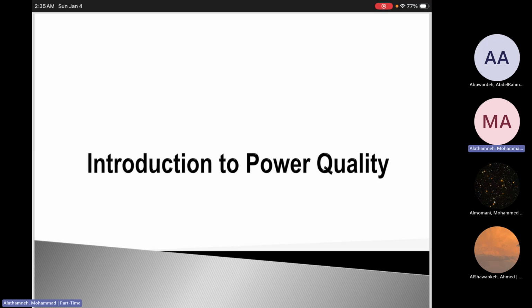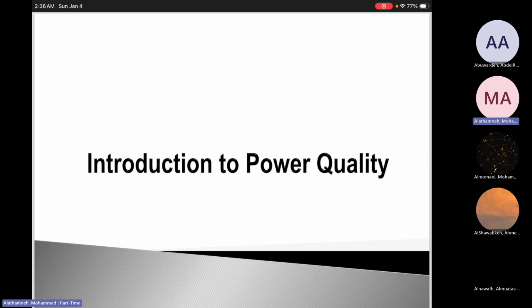In modern power systems, power quality matters more than ever, because loads don't look like the loads of the old days. In the past, the loads were basically motors, heaters, lamps, and fluorescent lamps. But today we have power electronics loads everywhere, like rectifiers, chargers, electric vehicle chargers, cell phone chargers, LEDs, computers, variable speed drives, and UPS systems. All of these devices are efficient and great, but unfortunately they are sensitive and sometimes they can create power quality issues. So power electronics is a source of bad power quality, and we can use it as well to solve power quality problems. Again, power electronics are considered a problem for power quality, and they can be used as well to solve it.